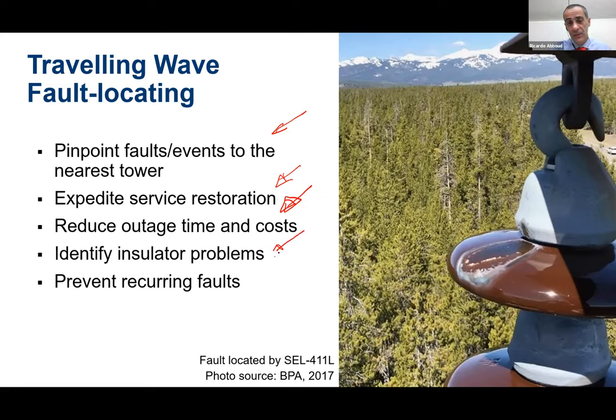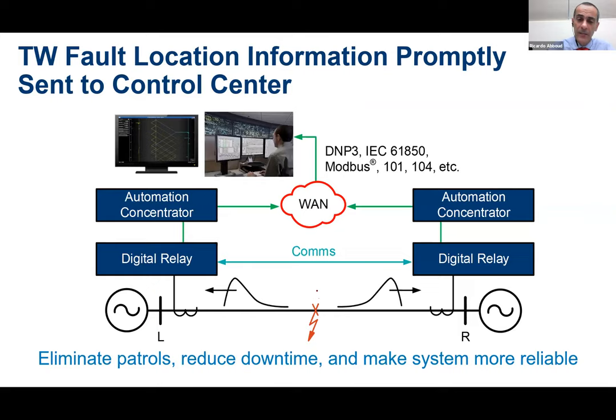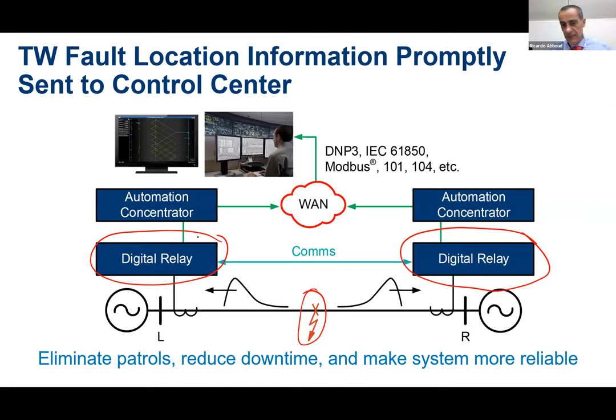As I'm saying, you can identify insulators with problems. This is one example: the maintenance people went directly to the tower where the problem is. And this is done in real time. When we have a fault in the transmission line, that fault launches traveling waves in both directions. The digital relays installed at both terminals of the line detect the traveling wave, use that information to locate the fault, and send the fault location to the control center immediately. Even before the breaker opens, that information can be sent, and the control center can dispatch the maintenance people or the patrol directly to the point of the fault.